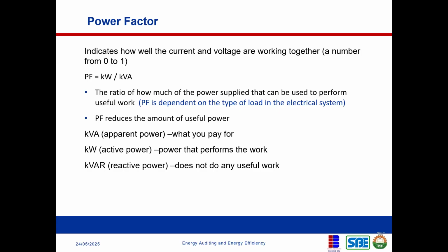Now, apparent power is kVA. Generators are rated in kVA because that's apparent power, all the power they can give, irrespective of what your power factor is. But the actual power you can get from that generator is where power factor comes in. Your power factor reduces what you can actually get from the generator. So this is what your generator can give.